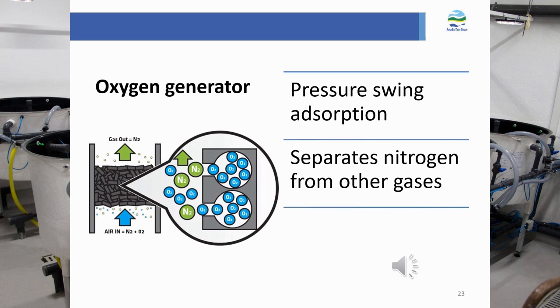The most common oxygen generators work on the principle of pressure swing adsorption (PSA), during which air passes through a carbon molecular sieve or zeolite and nitrogen binds to this media. Adsorption takes place in two separate pressure vessels, each filled with media, alternating between the separation and regeneration processes. Note that the gas produced by an oxygen generator is not only oxygen — carbon dioxide and other gases from the air can also be present.